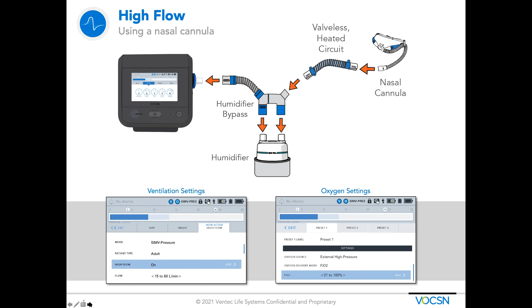What's important is this, and I'm going to show you two more slides and then I'm going to stop, is that for high flow nasal cannula, you need this valveless heated circuit. My perception from a couple people I talked to was they'd never seen the ventilator before, and the different circuits were confusing. So it's really simple to set it up once you've been shown how to do high flow nasal oxygen. But the device, very similar to modern devices used in this area, can also do non-invasive ventilation with a face mask and has the ability to compensate for leaks.